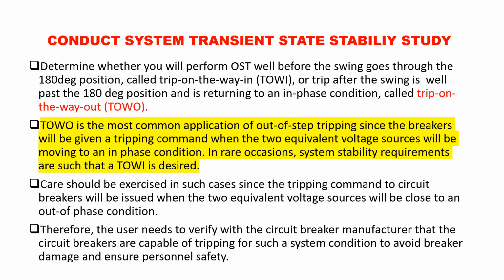And there is another one, which is the trip after the swing, that is, if the system has passed the 180-degree position and then returns to the in-phase condition, this is known as the trip on the way out. So this phenomenon I have explained in my classroom settings, how the power swing locus enters into the tripping zones of the distance relay, and it can either return out of the characteristic, or it can keep on penetrating into the system. So in both cases you can have the tripping.